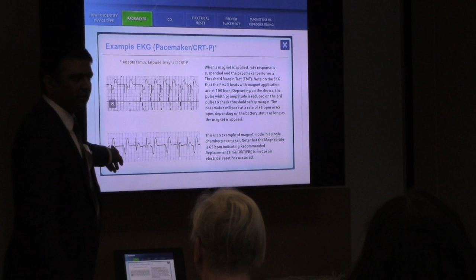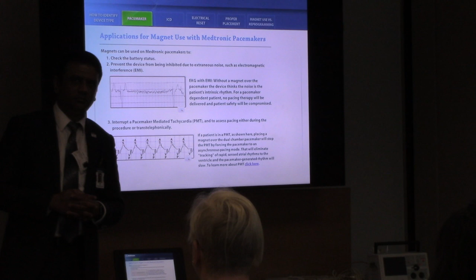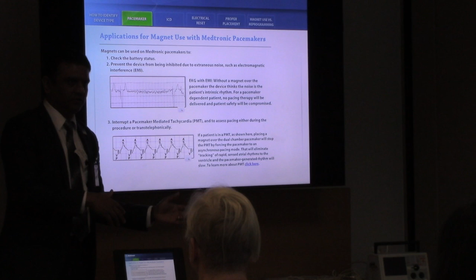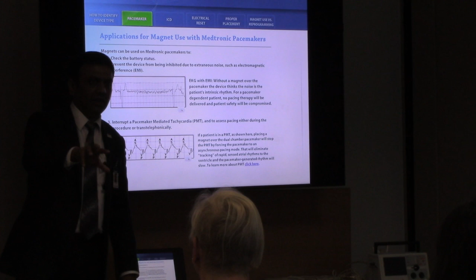So, why would you put a magnet on during surgery, do you think? Can anybody guess? Why would a magnet be useful? Is it because of the electrical cautery they use? So, what do you think the cautery would do? It would affect the way the pacemaker is moving? So it all harks back to the NBG code, right? So you're always in some kind of sensing mode when you don't have the magnet on. The magnet puts it in an asynchronous mode, which won't sense anything, right?